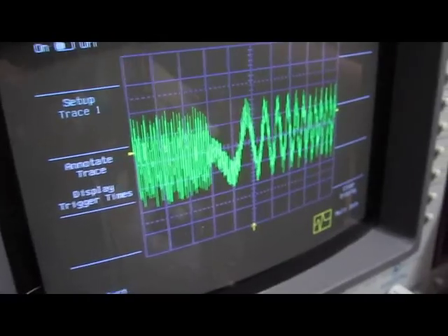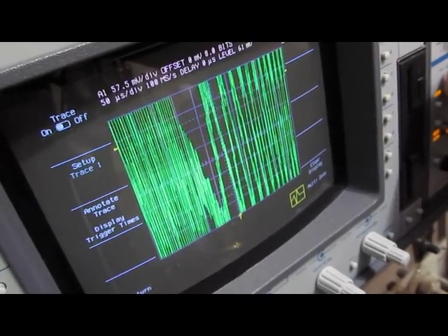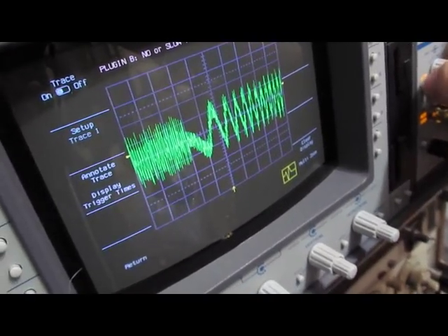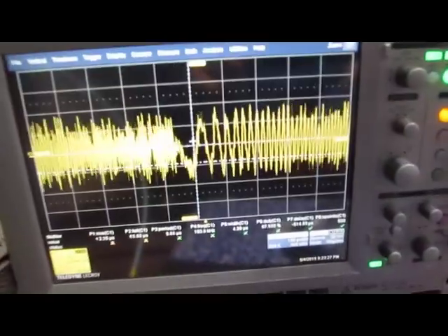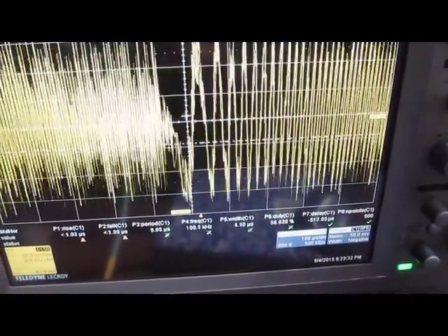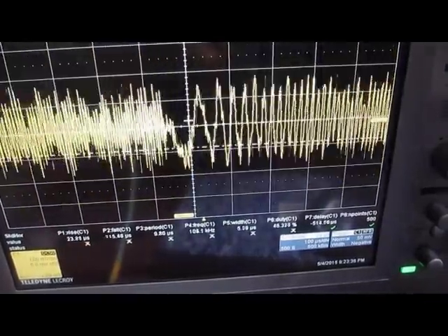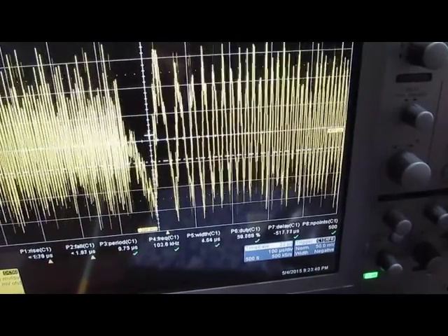So you're looking at the 7200. Here you're looking at 20 millivolts, 50 millivolts, 0.1 volts. It's just very solid. The WaveRunner, it's not the case. You can just see here as I increase the amplitude, it starts behaving very erratically.